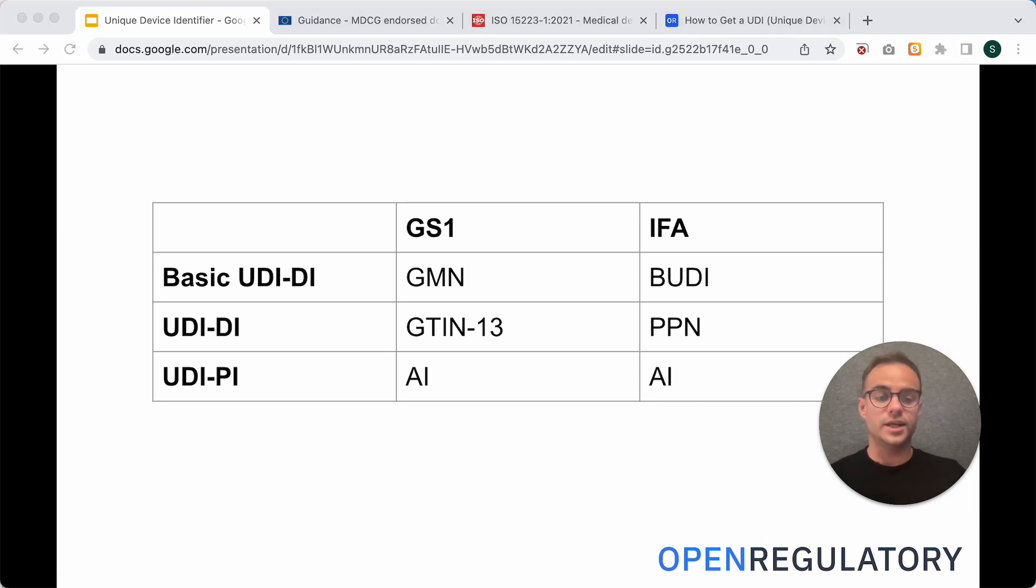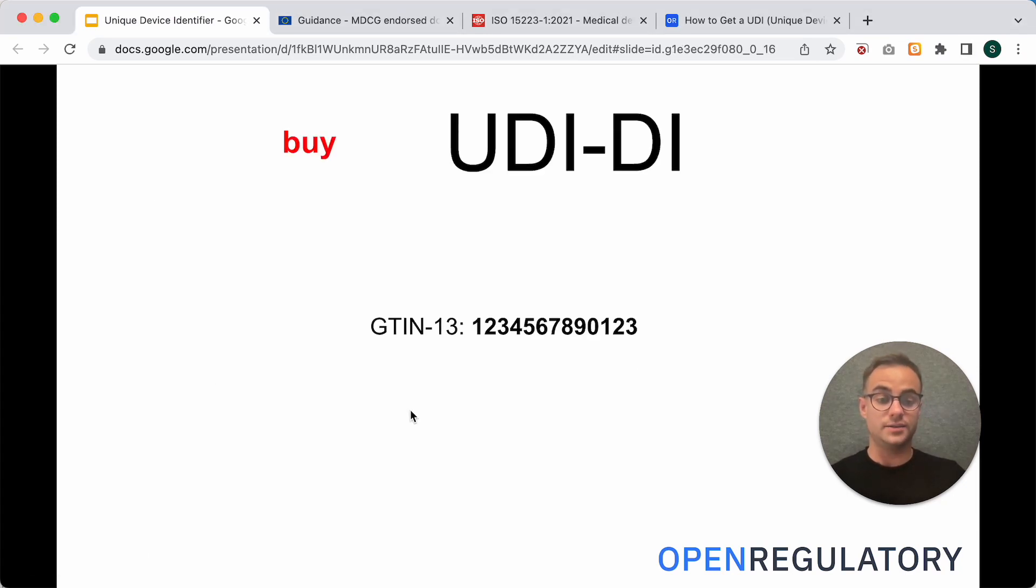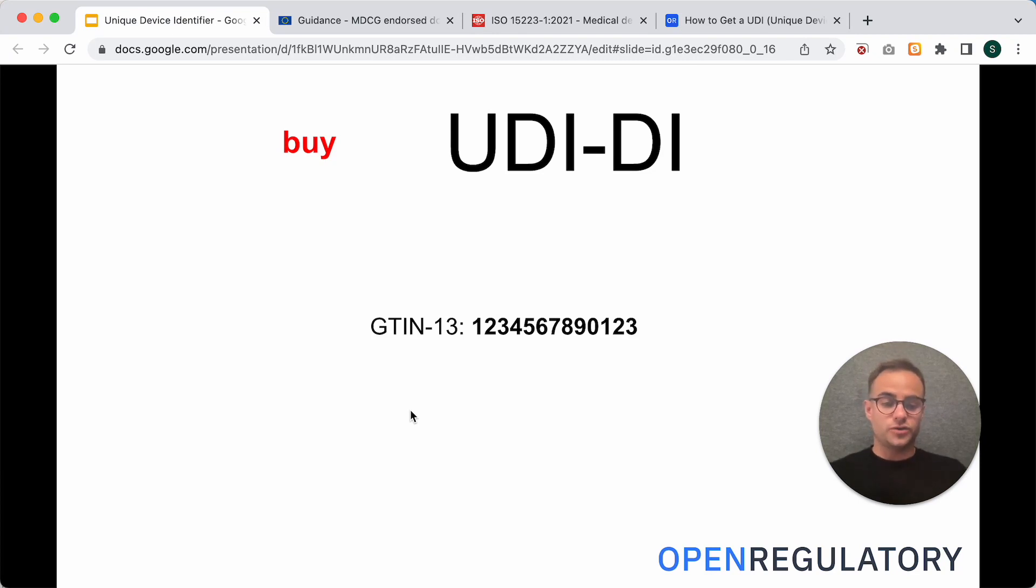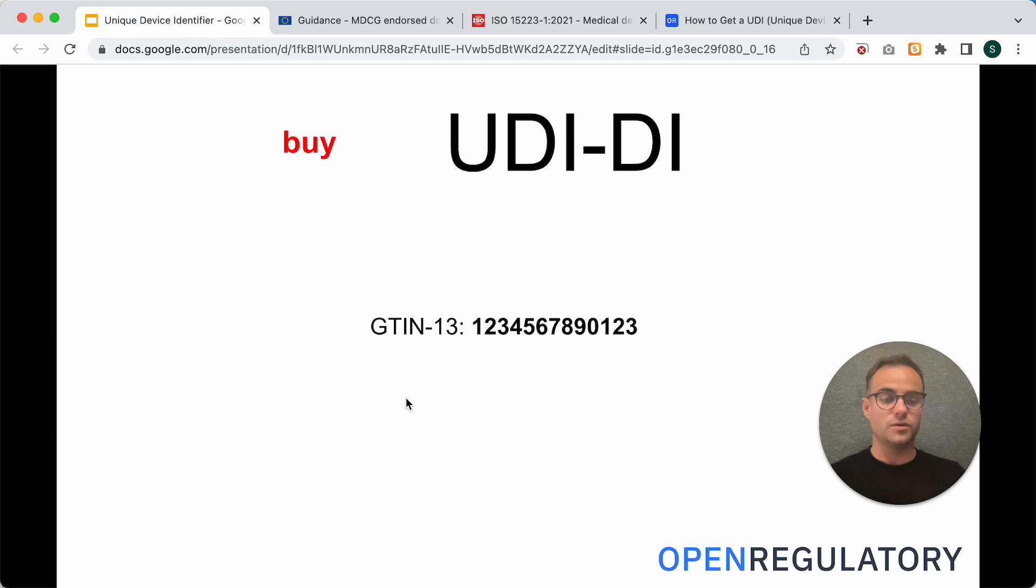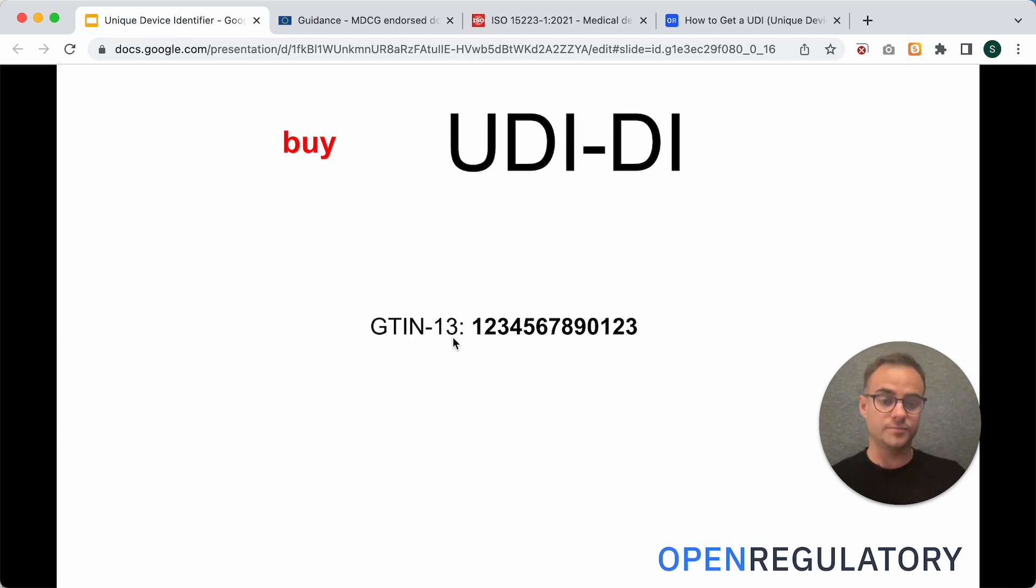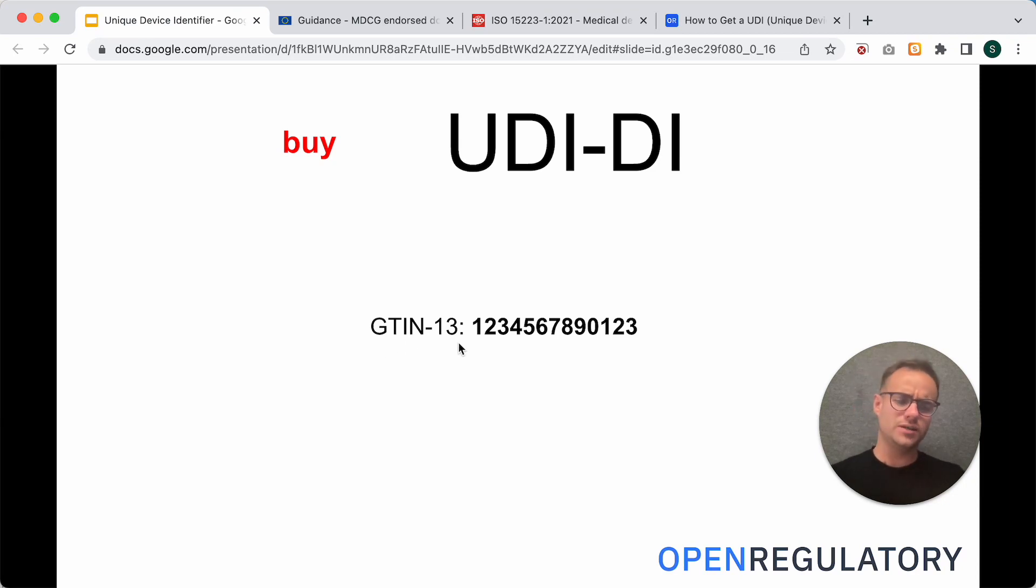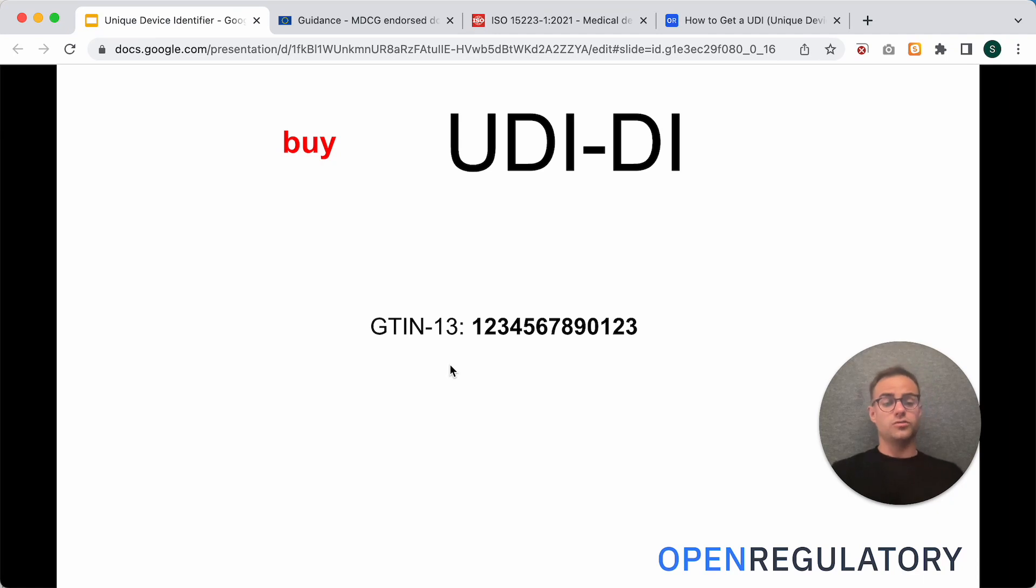Now, let's take a look at the UDI-DI. This is the first thing that you need to buy, and if you buy it at GS1, you will get a GTIN-13. Sometimes you will also get a GTIN-14, but that's not really relevant here, because this is more for Northern America.